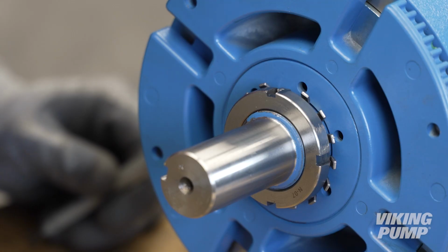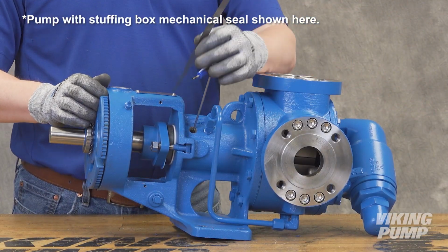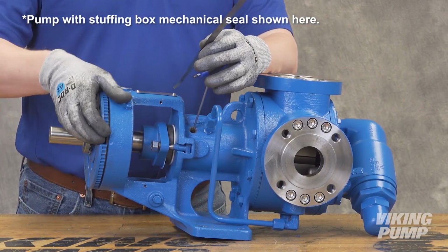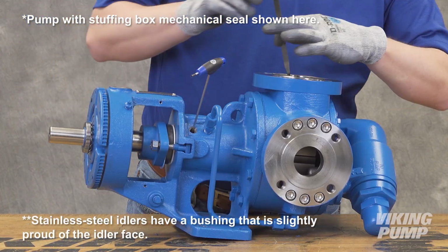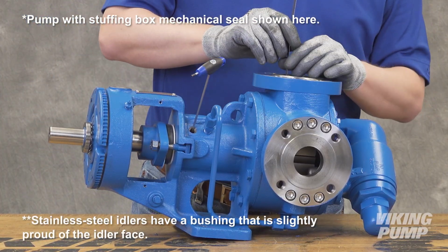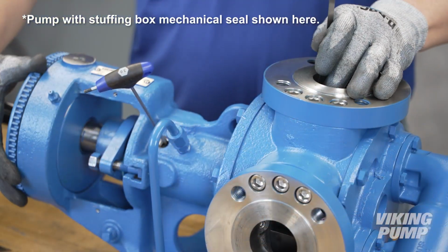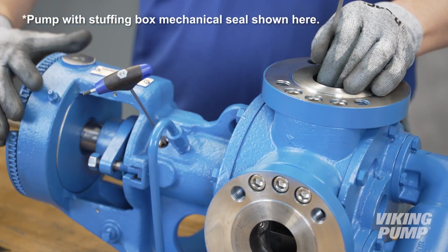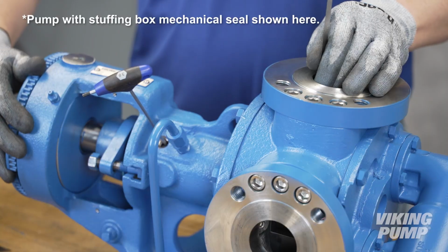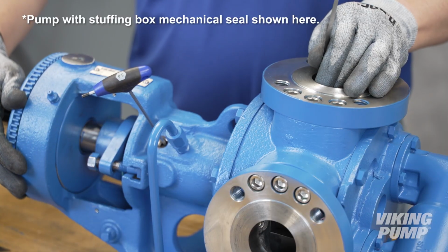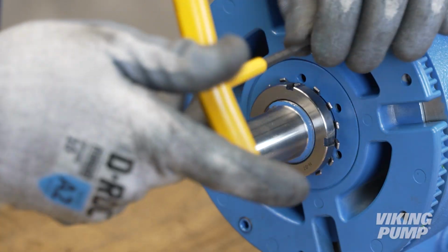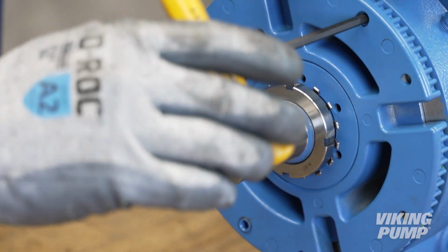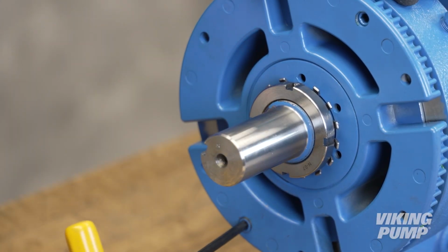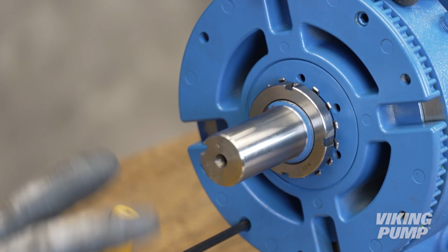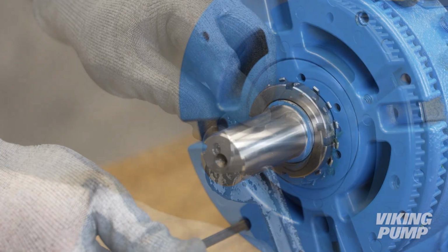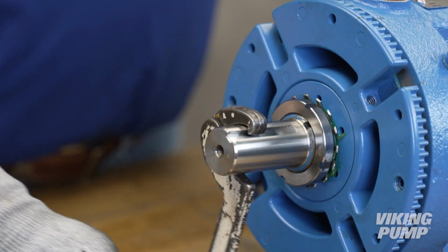Now set the end clearance. The end clearance setting can be found in the technical service manual. Loosen the bearing housing and insert the appropriate feeler gauge between the rotor face and idler bushing. Tighten the bearing housing until there is a slight drag when moving the feeler gauge between the face of the rotor and idler bushing. Once end clearance is set, tighten the two set screws in the face of the bearing housing. Turn the shaft to ensure the pump turns freely.